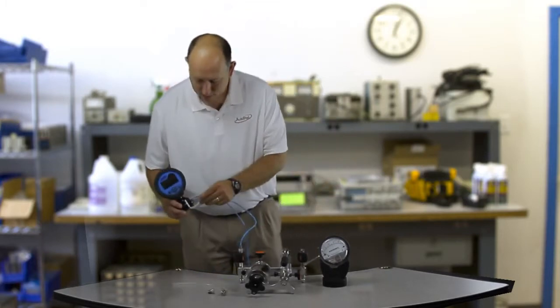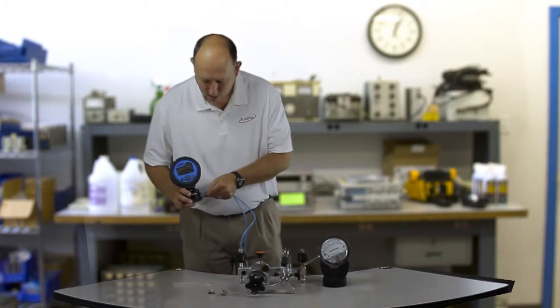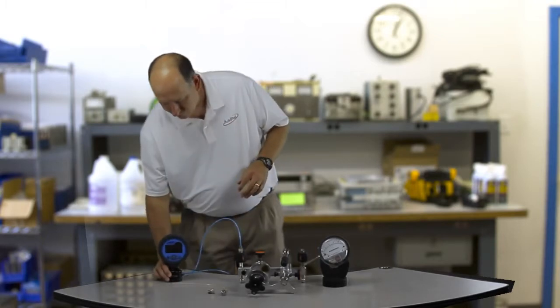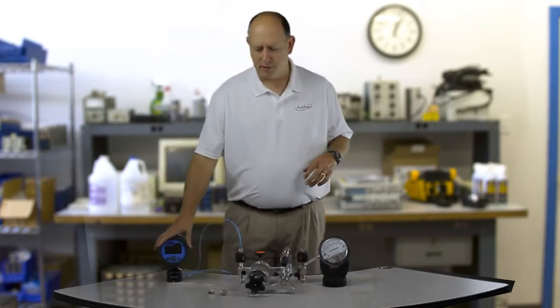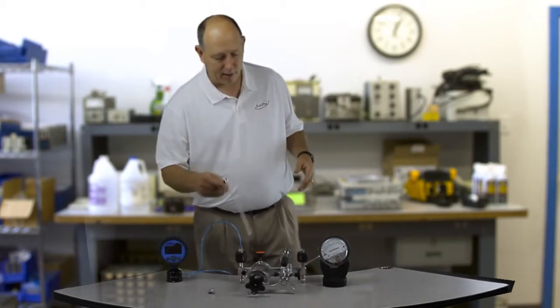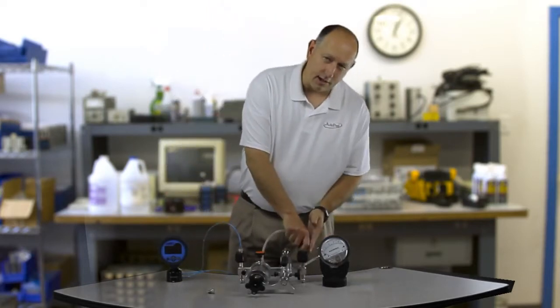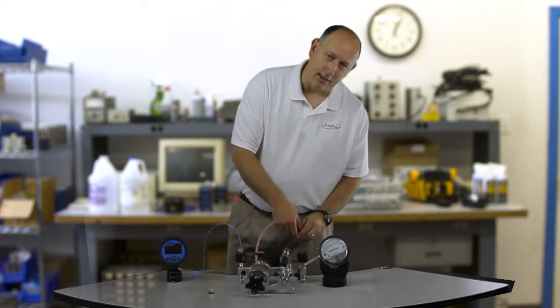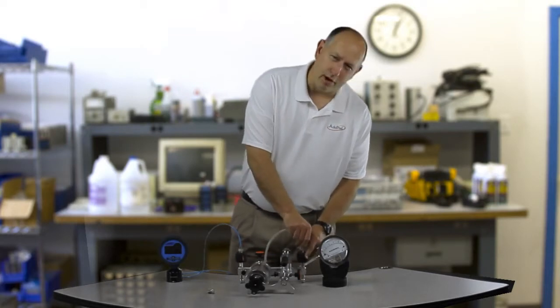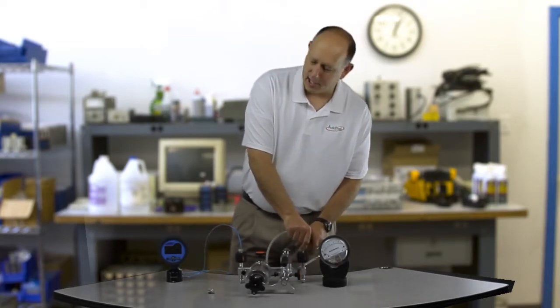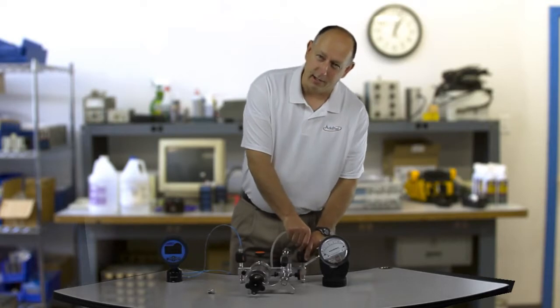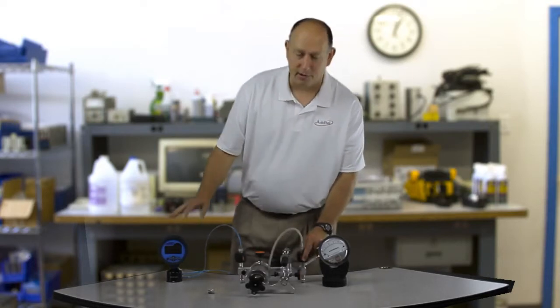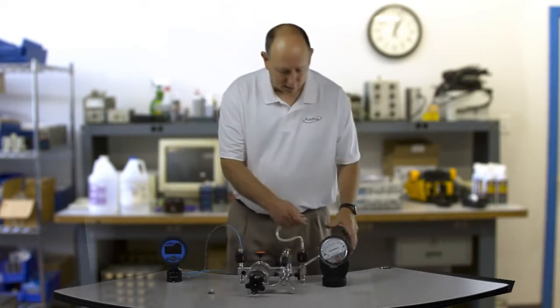Now I'm going to tie that to the high side of the reference gauge. One thing I failed to mention is that I want to zero my reference gauge before I plug in all this tubing, because at such low pressures, even plugging in the tubing generates some pressure. If I zero it after hooking everything up, I'd be introducing an error. So I zero my reference gauge before I plug everything in.